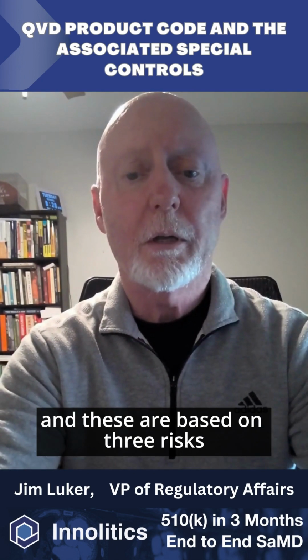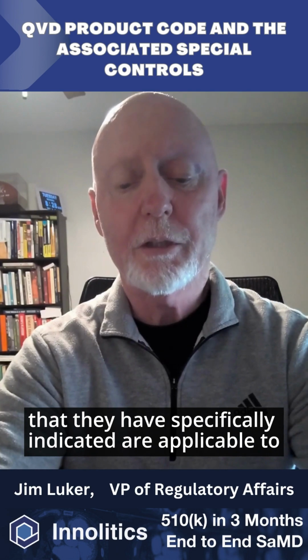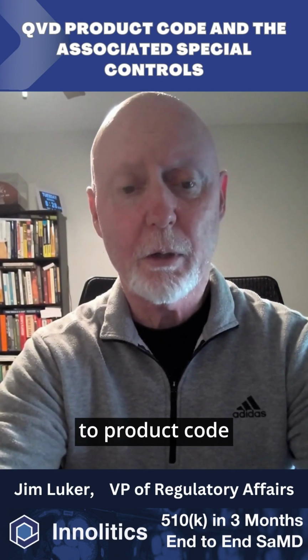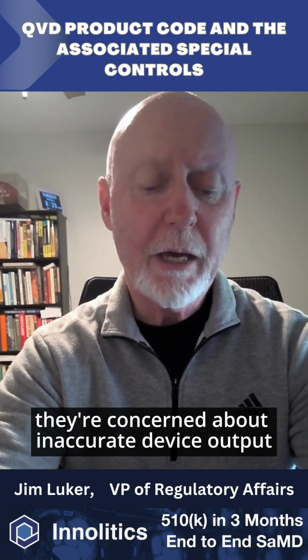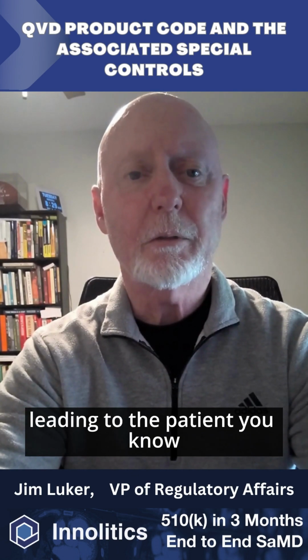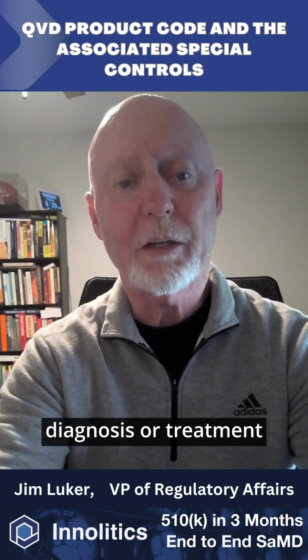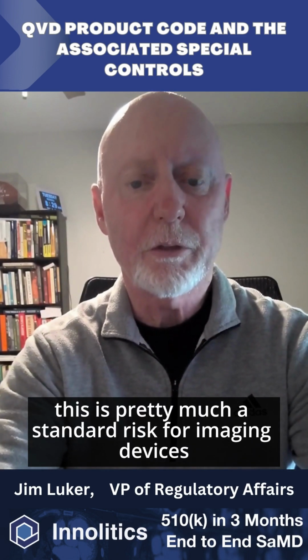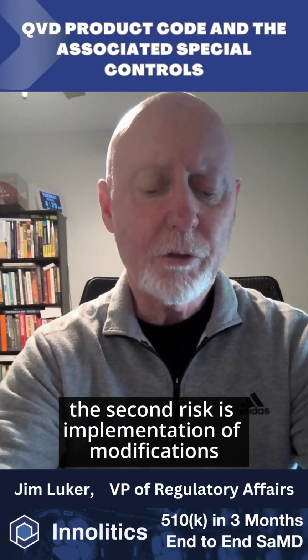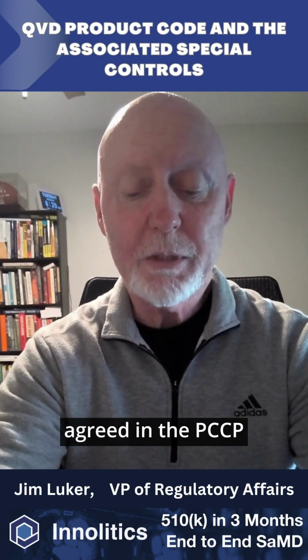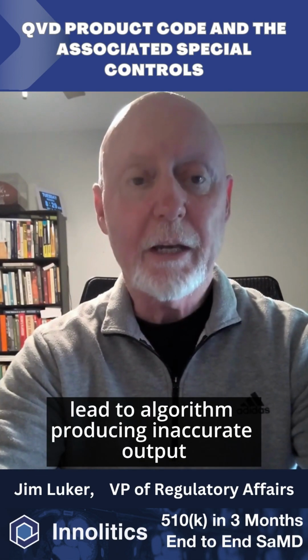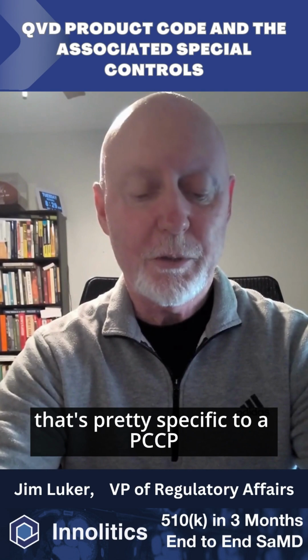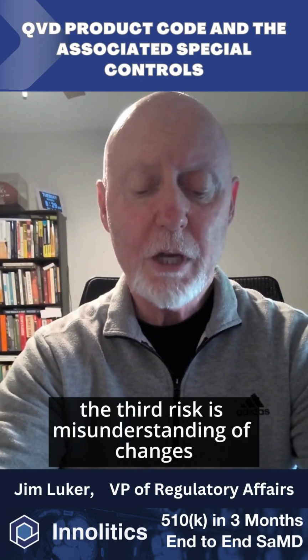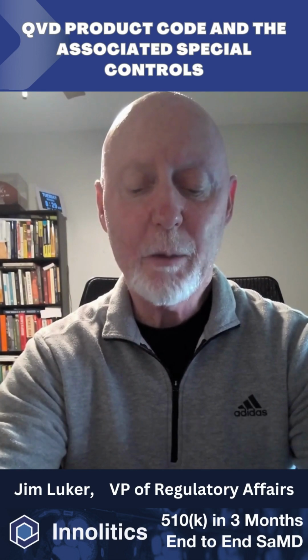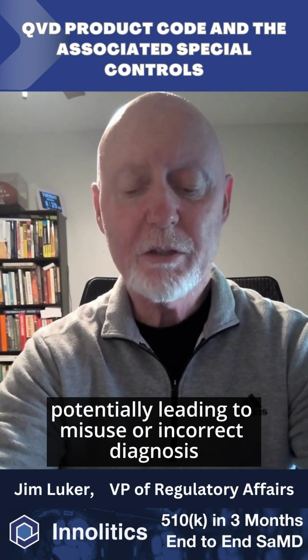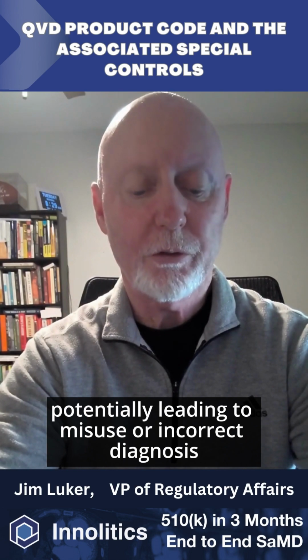And these are based on 3 risks that they have specifically indicated are applicable to this product code with the PCCP. They're concerned about inaccurate device output leading to the patient receiving inadequate or incorrect diagnosis or treatment. This is pretty much a standard risk for imaging devices. The second risk is implementation of modifications agreed in the PCCP leading to the algorithm producing inaccurate output. That's pretty specific to a PCCP. The third risk is misunderstanding of changes to the device input criteria, output criteria, and output performance, potentially leading to misuse or incorrect diagnosis or treatment.